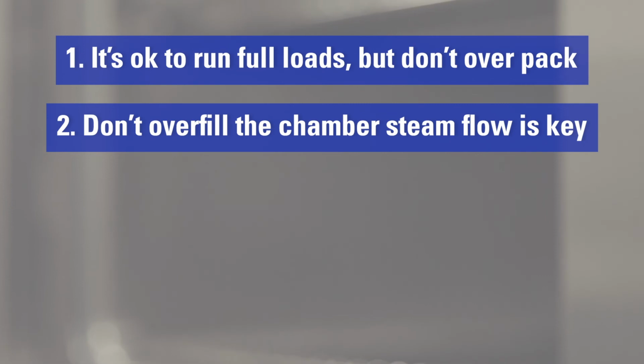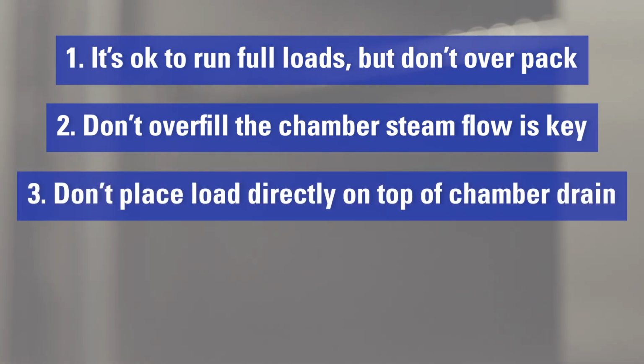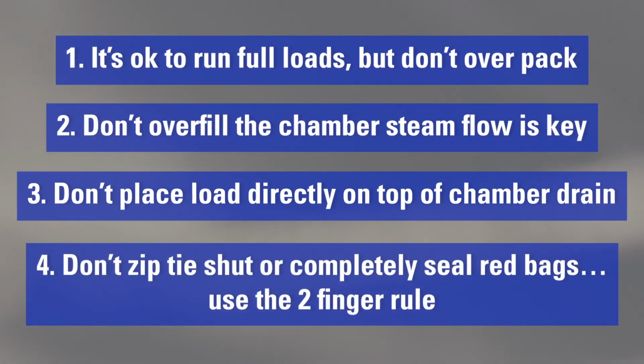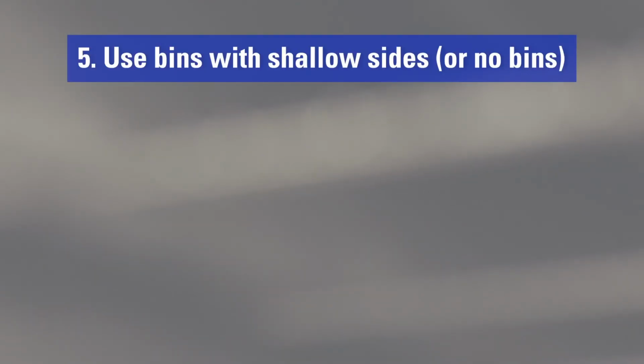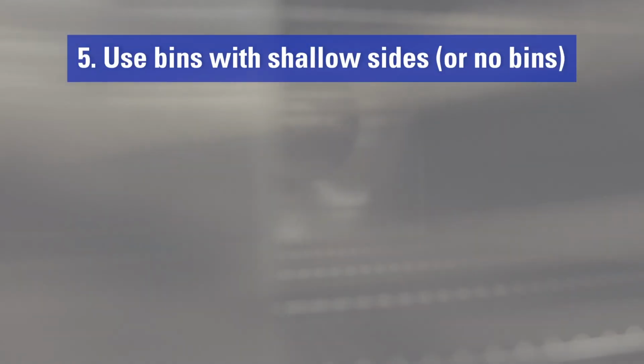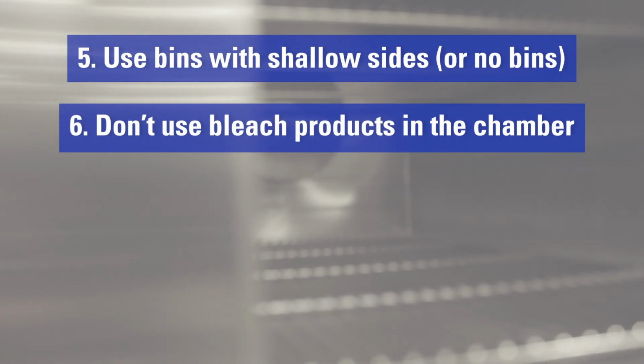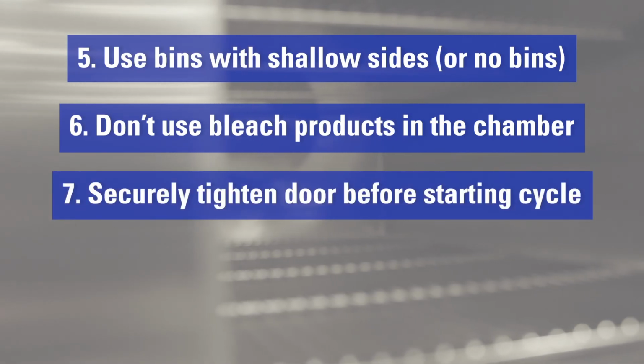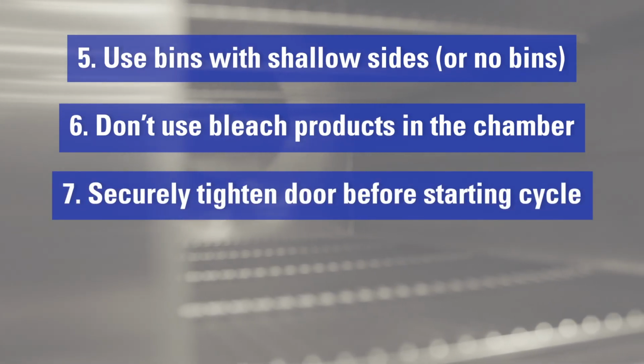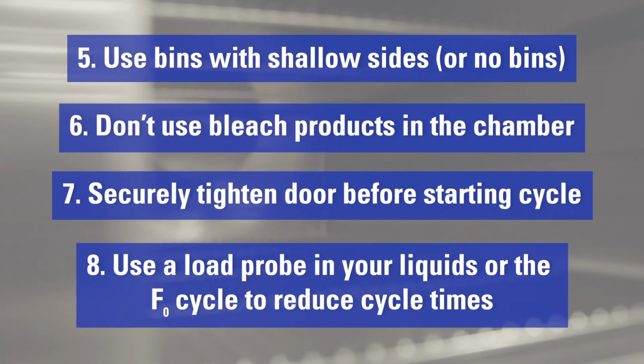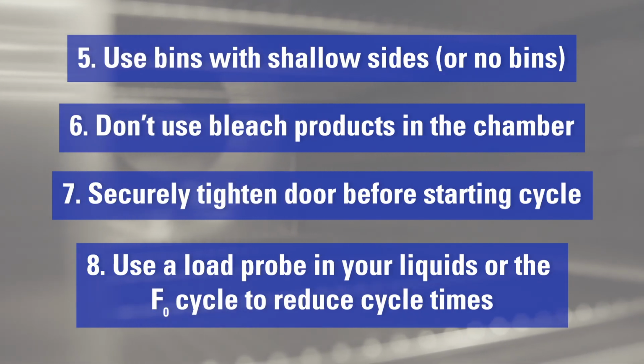Here are some tips and tricks for running your autoclave. It's okay to run full loads, but don't overpack. Don't overfill the chamber, steam flow is key. Don't place loads directly on top of the chamber drain. Don't zip tie shut or completely seal red bags. Use the 2-finger rule. Use bins with shallow sides. Don't use bleach products in the chamber. Securely tighten the door before starting the cycle. Use a load probe in your liquids or the F-Sub-Zero cycle to reduce cycle times.